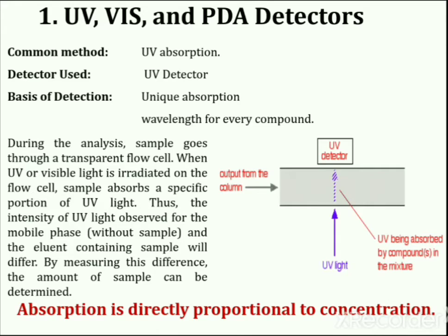Since the ultraviolet absorbance detection method involves detection at a specific wavelength, it is important to choose an appropriate wavelength based on the type of analyte. A standard UV detector allows the user to choose wavelengths between 180 to 380 nm. A visible detector uses longer wavelengths, around 400 to 700 nm. Detectors which provide a wider wavelength region are called UV visible detectors, and they cover the combined range of 180 to 700 nm.